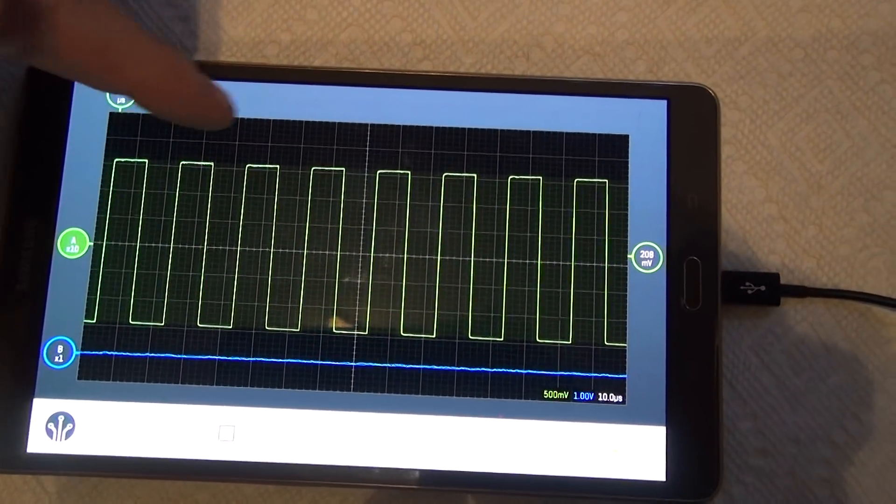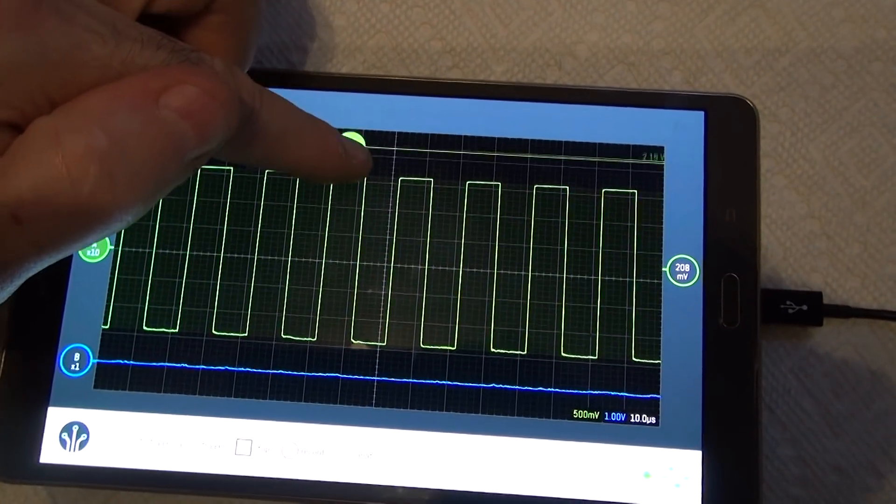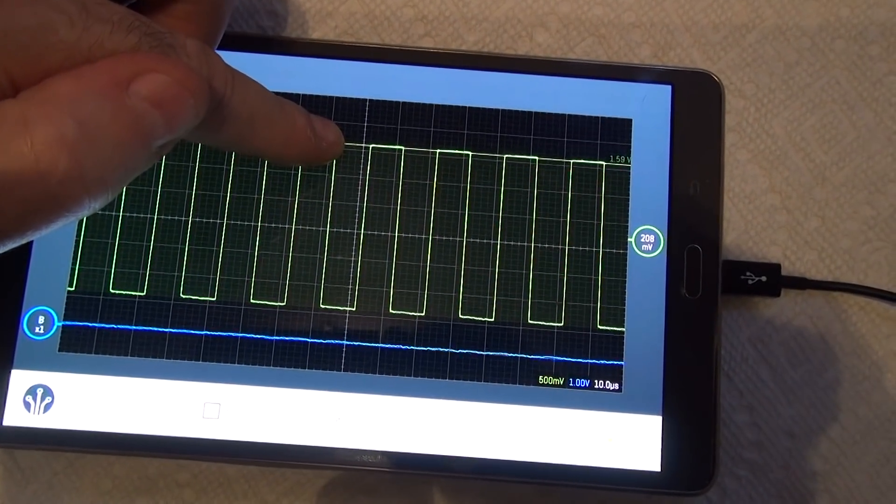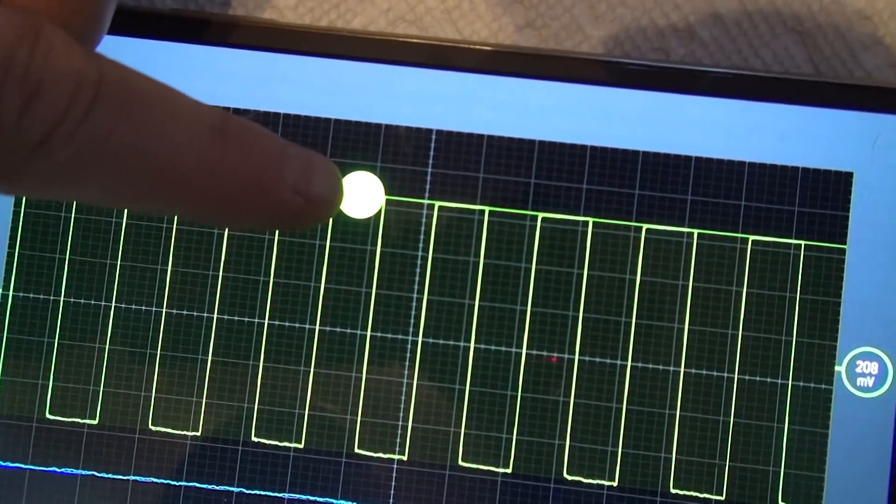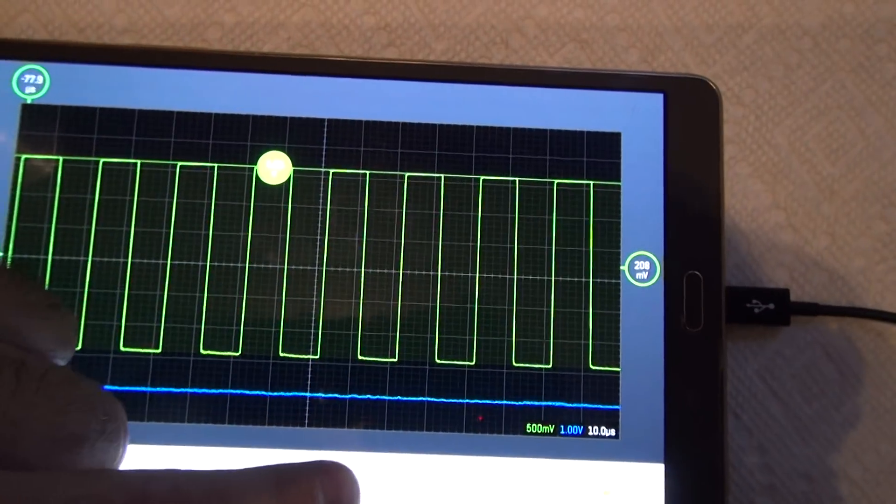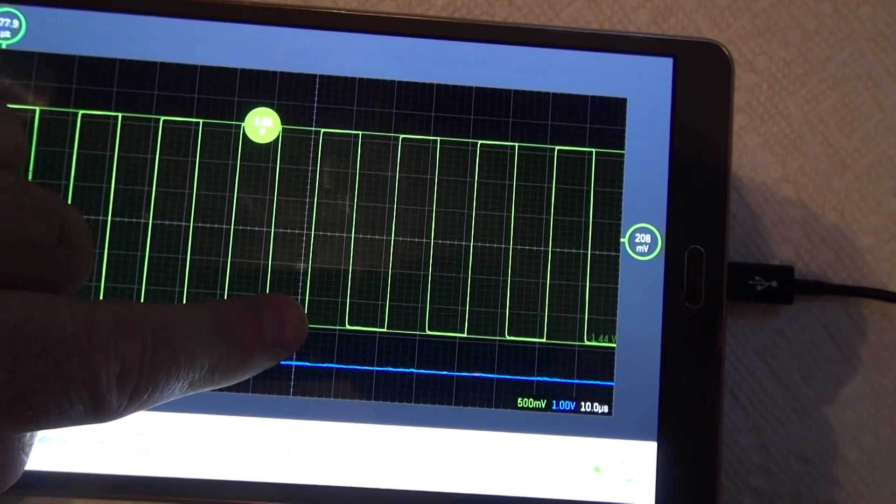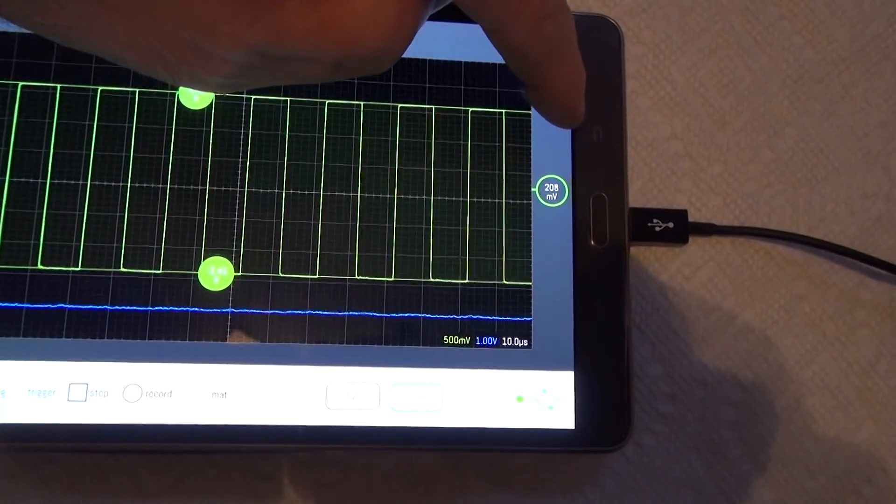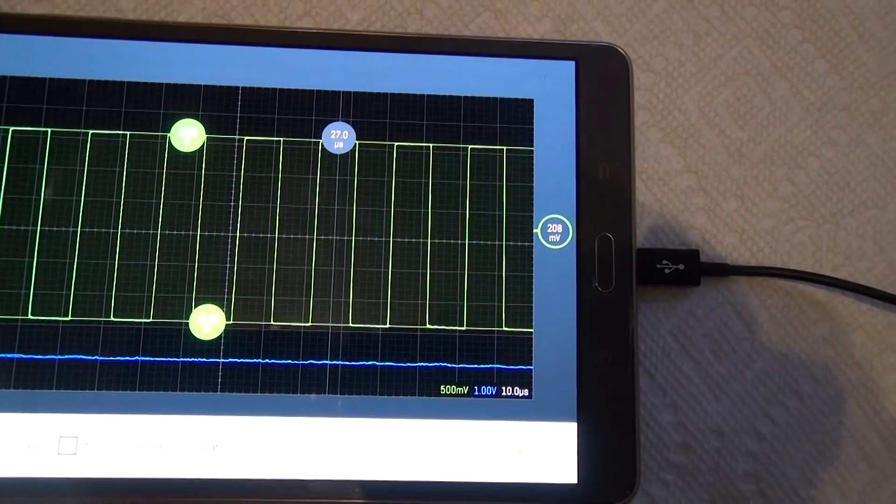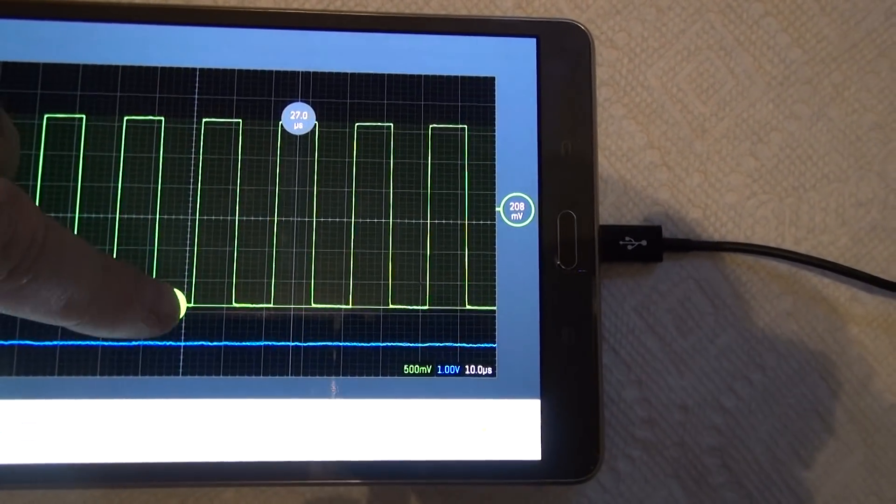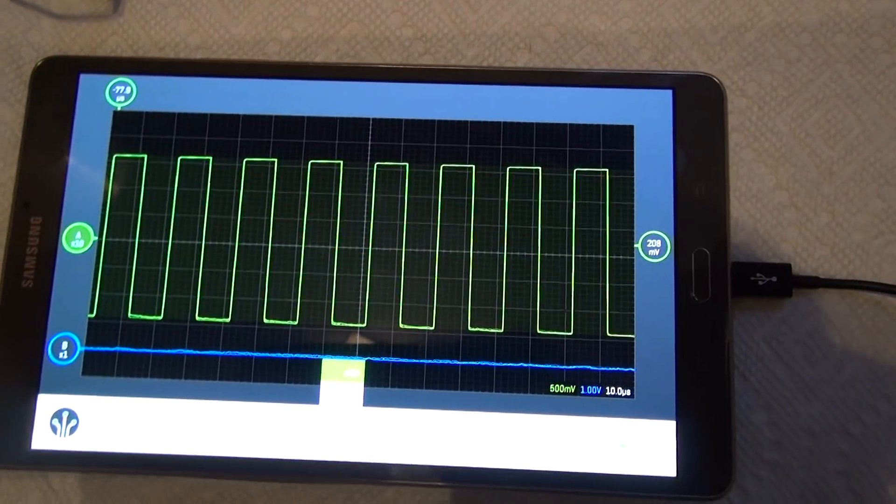You've got cursors. All you have to do to get a cursor measurement, either amplitude or time, is you just drag in from the edge of the screen. You place the cursor where you want it. That says 1.16 volt for that cursor. I can drag another one in from the bottom of the screen. If I put that on the bottom of the waveform it tells me minus 1.41. If you want to measure time base you drag in from the left and right side of the screen, place it wherever you want it. I'm going to place it in between pulses so you can see the line. You can do as many of these cursors as you want. You just keep dragging them in. If you don't want them you drag them off the screen.